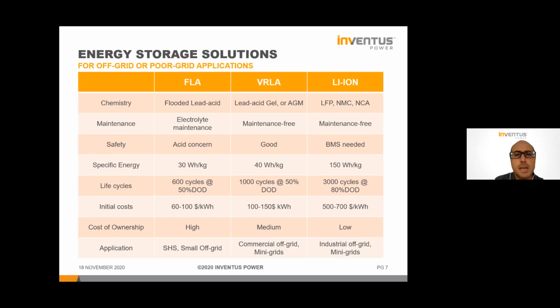Though lithium batteries need a BMS, the battery management system, which was already introduced by Pablo. It's the brain of the battery and controls everything, protecting it from overvoltage, high and very low temperatures, and high discharge or charge currents. The BMS is really needed in a lithium-ion battery, because otherwise the battery could run into thermal issues - you've probably seen how lithium batteries can explode. That's why the BMS has to be very high quality, with high quality components, and you should rely on a very good BMS.